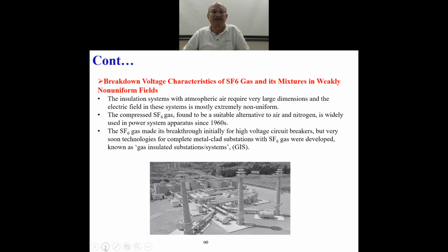Even in the gas, we do not want any partial breakdown activity because it will degenerate the gas and the insulating properties of the gas. So when we adopted SF6 gas as an insulant, efforts have been made to remain within the weakly non-uniform field configuration.